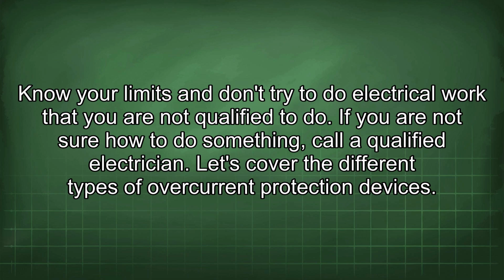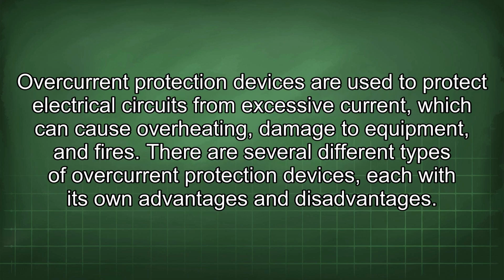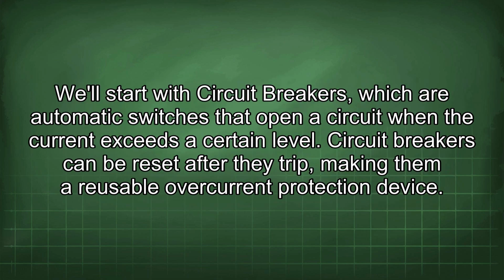Let's cover the different types of overcurrent protection devices. Overcurrent protection devices are used to protect electrical circuits from excessive current, which can cause overheating, damage to equipment, and fires. There are several different types of overcurrent protection devices, each with its own advantages and disadvantages. We'll start with circuit breakers, which are automatic switches that open a circuit when the current exceeds a certain level. Circuit breakers can be reset after they trip, making them a reusable overcurrent protection device.